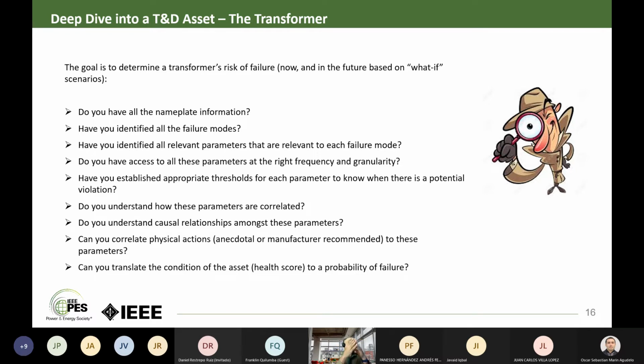And then can you look at the next step, which is, can you correlate the physical actions, in this case anecdotal or manufacturer recommended, to these parameters? For example, we know that if transformers are made at a particular age, the paper used in there is of a material that is subject to more failures than if another material is used. So do we have that sort of expertise related to the transformer from a design perspective?